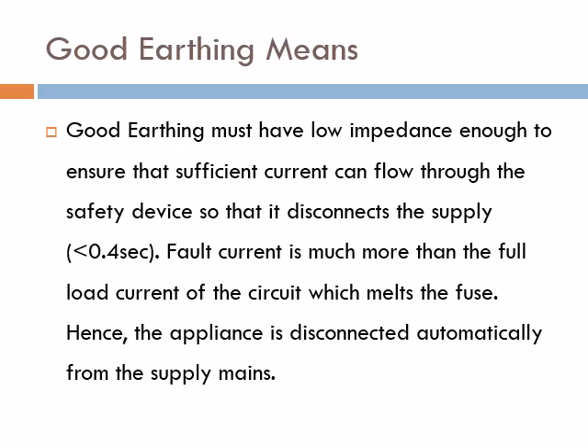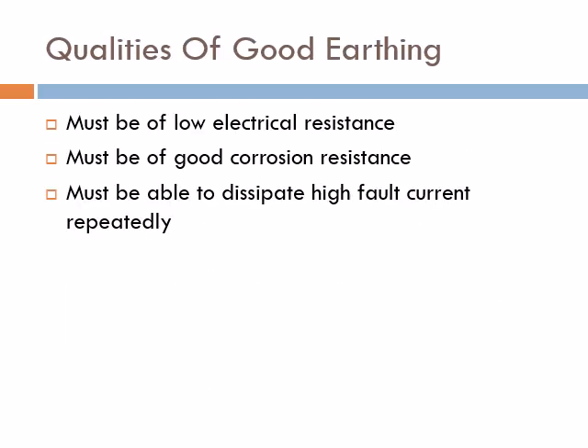What does good earthing mean? Good earthing must have low impedance, which is enough to cut off the current in a quick time, that is less than 0.4 second. Then the fault current is much more than the full load current of the circuit, which melts the fuse. Hence the appliance is disconnected automatically from the supply mains.